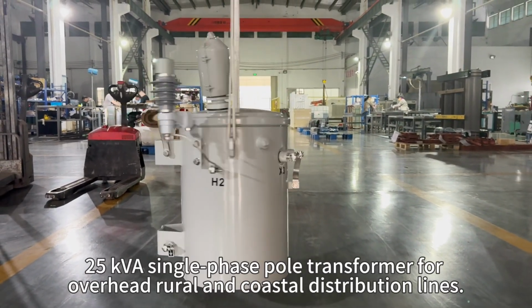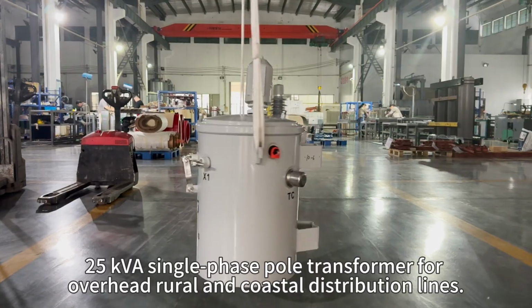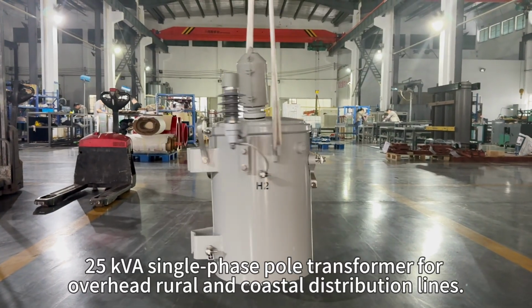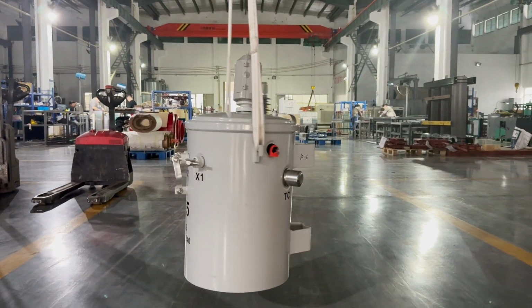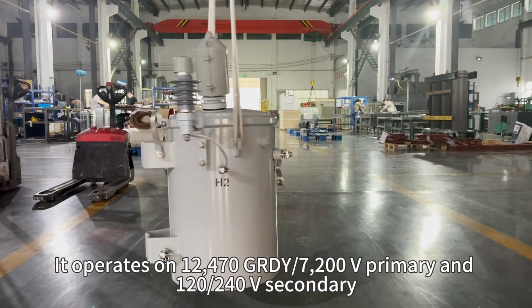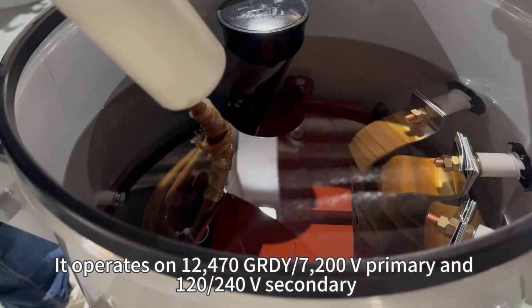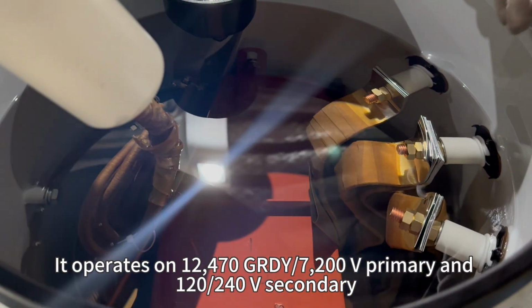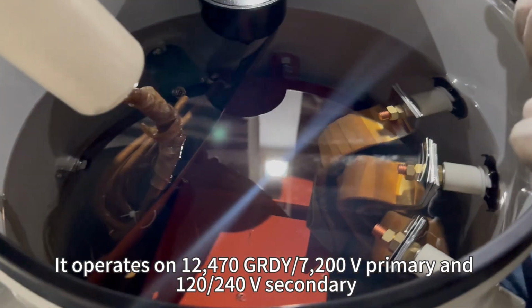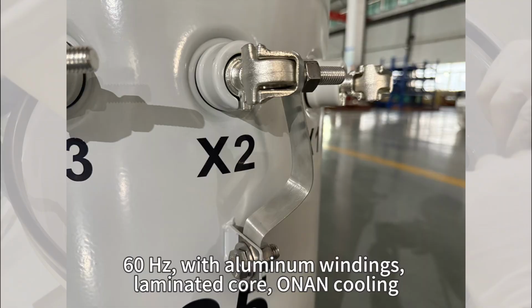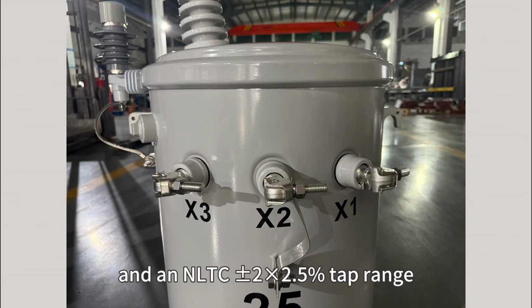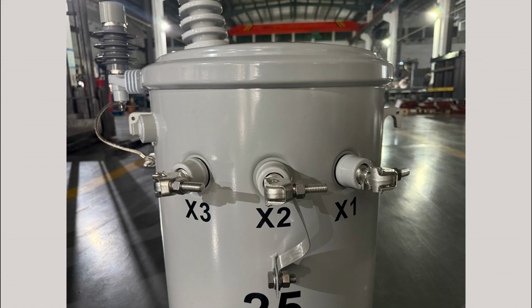25 kVA single-phase pole transformer for overhead rural and coastal distribution lines. It operates on 12,470 GRDY 7.2 primary and 120/240 V secondary, 60 Hz, with aluminum windings, laminated core, ONAN cooling, and an NLTC 5 tap range.